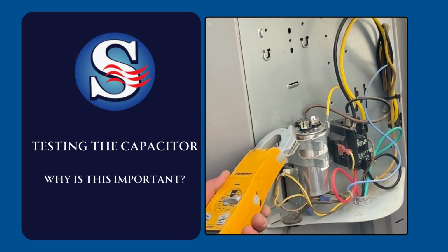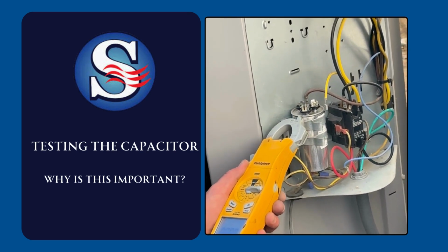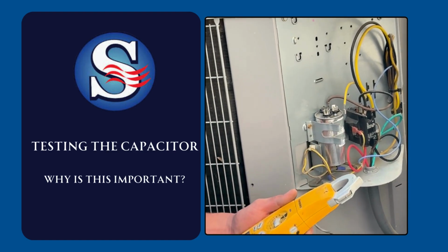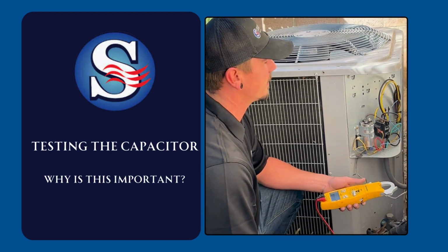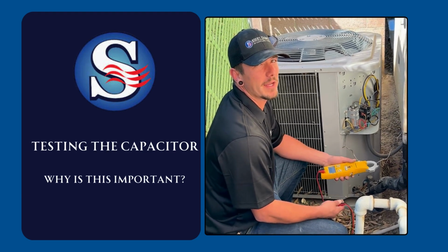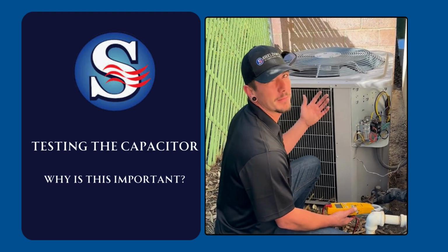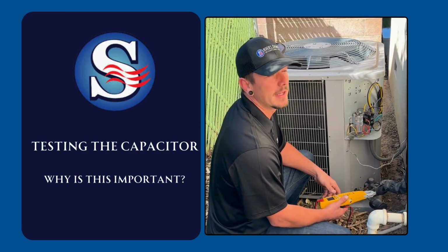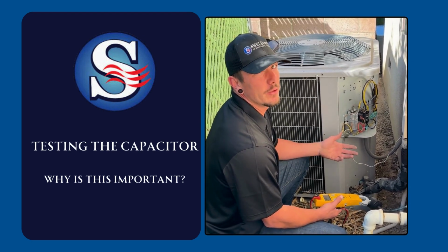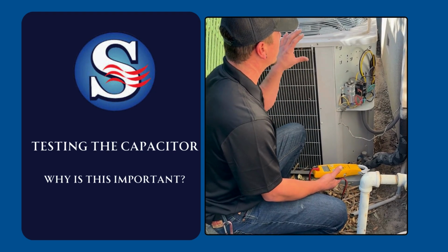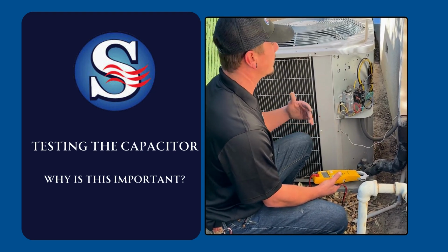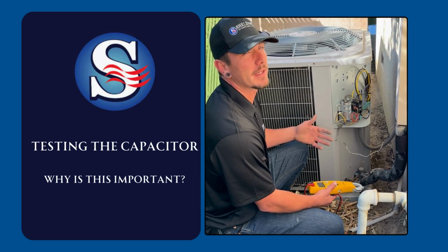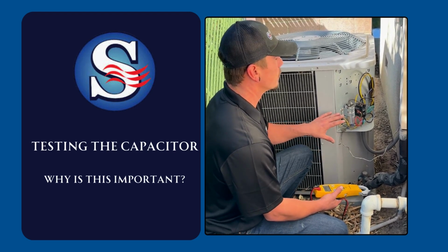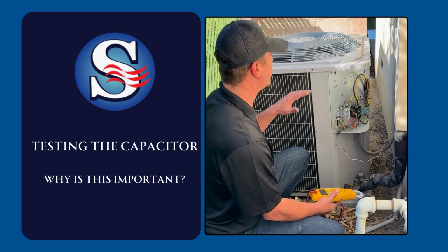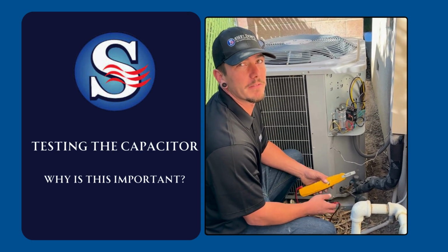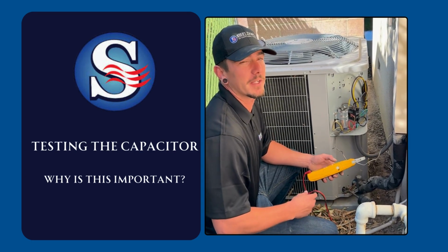This is one of the number one failures in the outdoor units. It's kind of a consumable part because it doesn't last forever. Over time, they start to get weaker, and as they get weaker, they're going to cause the motors to struggle to operate. When they do get weak, they do cause wear. That's why even though the system may be starting, technicians will recommend replacing them because they're getting weak. And it is crucial to keep them good because, like I said, they will cause damage to the motors if they aren't within manufacturer specifications.